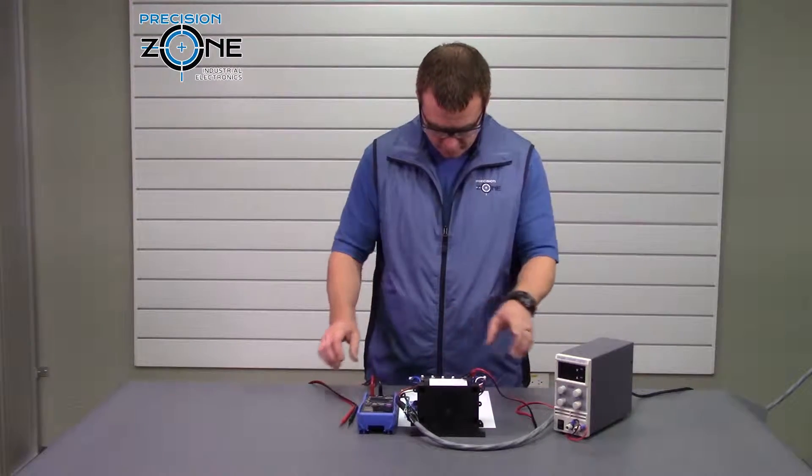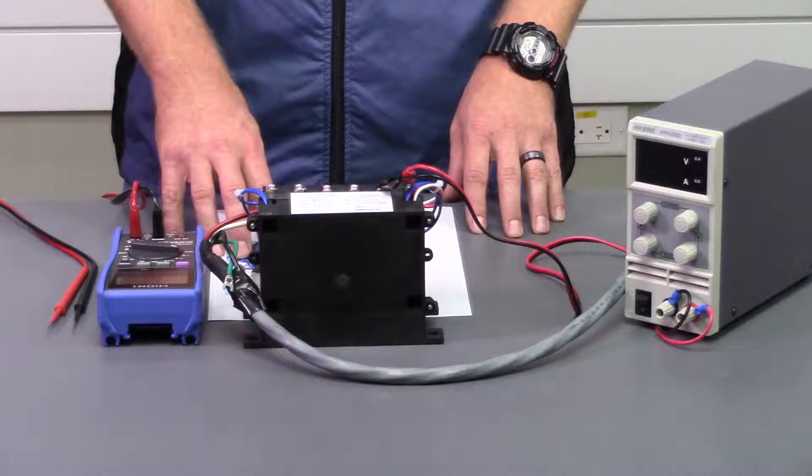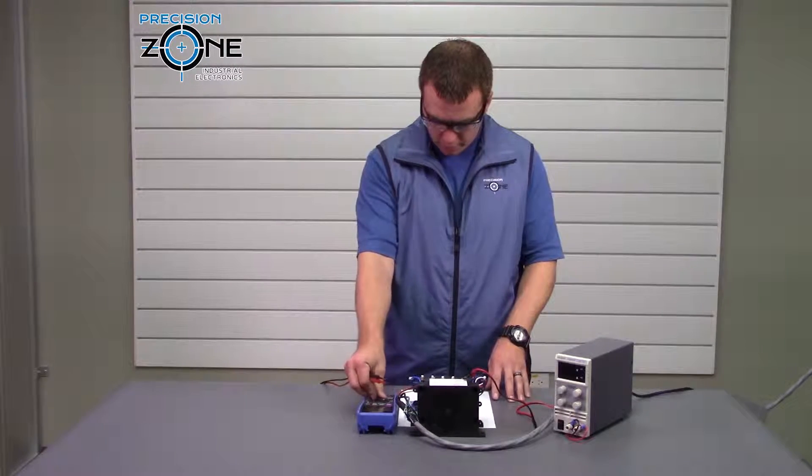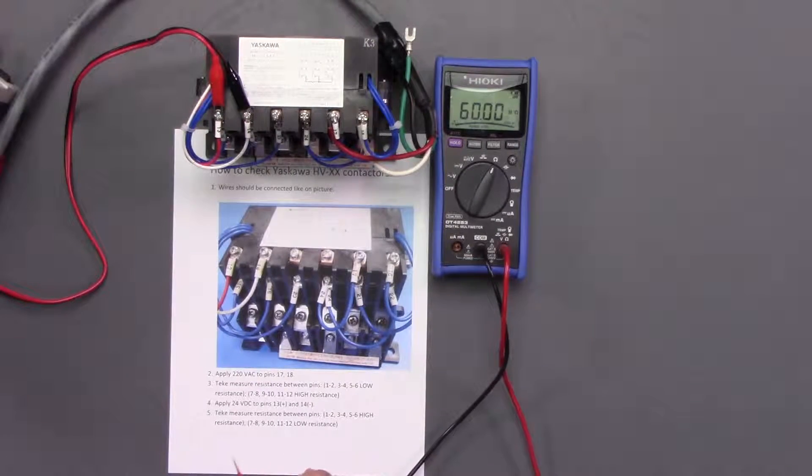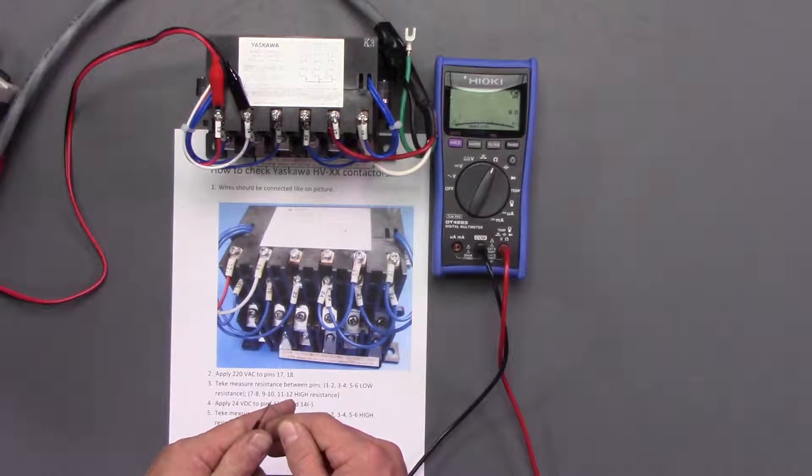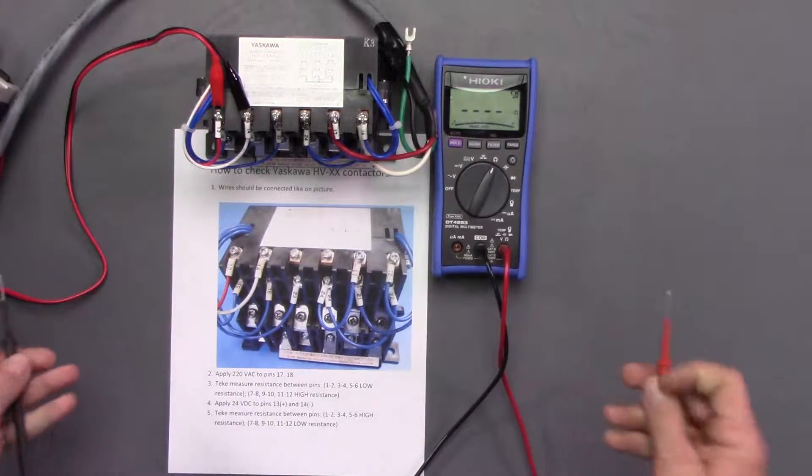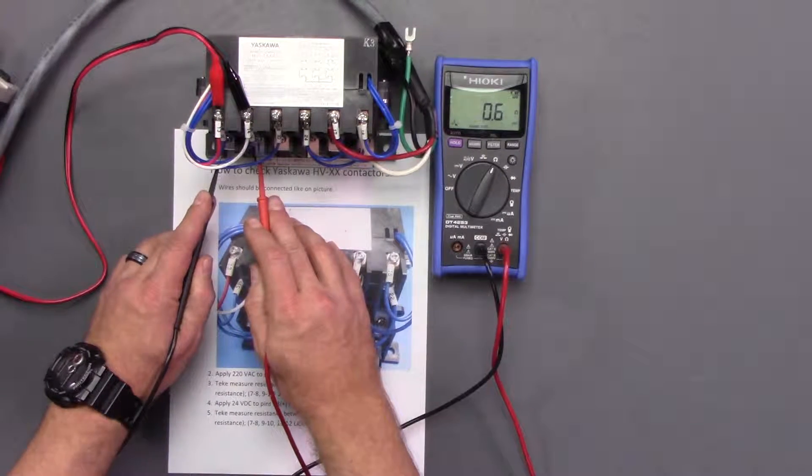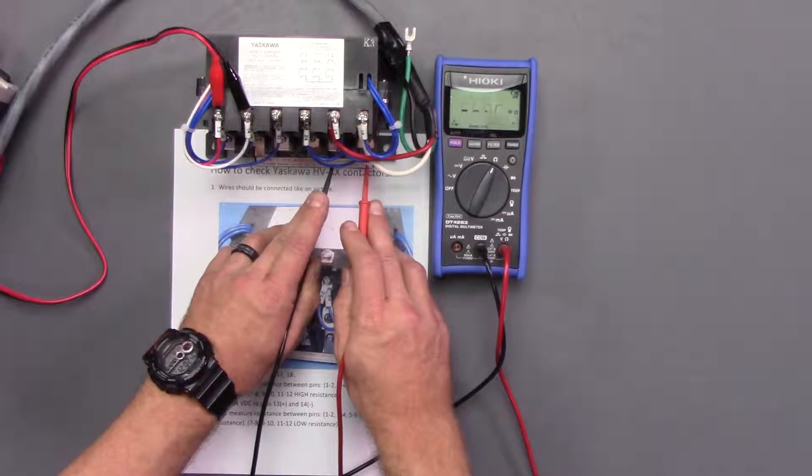So now that we know we have this energized, this procedure that's here in front of me comes right from us at precisionzone.com. We're going to move to the resistance function and it says take a measurement resistance between 1 and 2, 3 and 4, and 5 and 6, low resistance. So we're just going to touch our leads together and see we're getting 0.6. So it shouldn't be much more than that. 1 and 2, 3 and 4, 5 and 6.